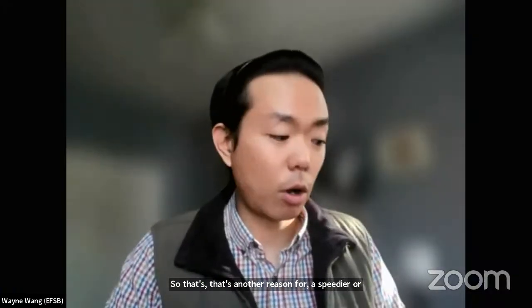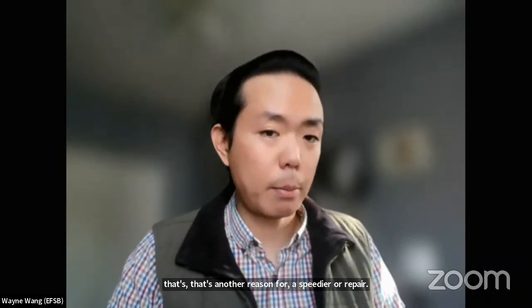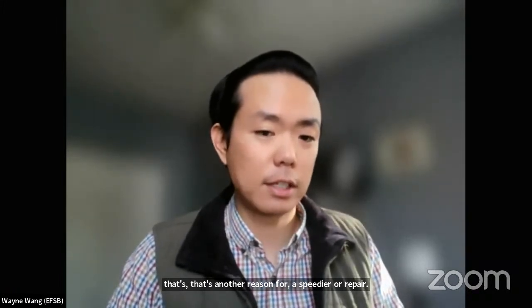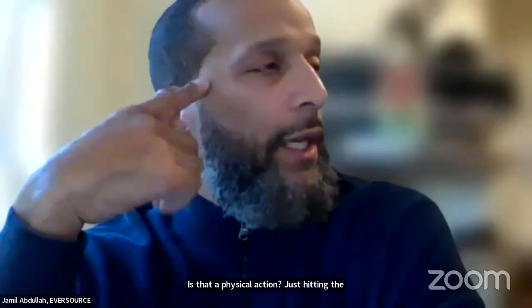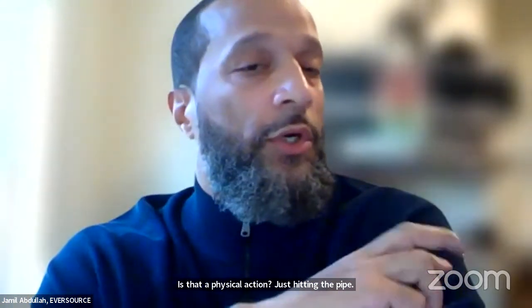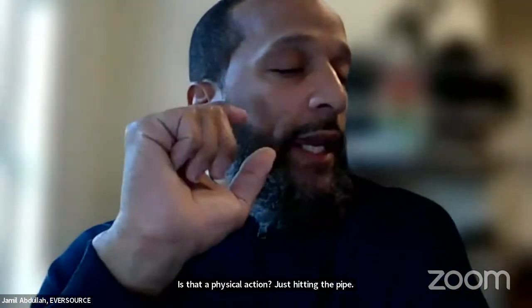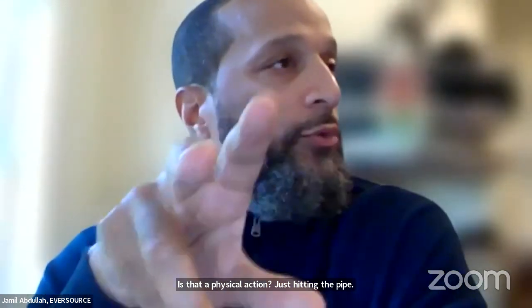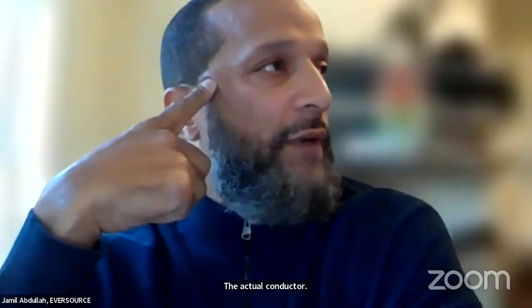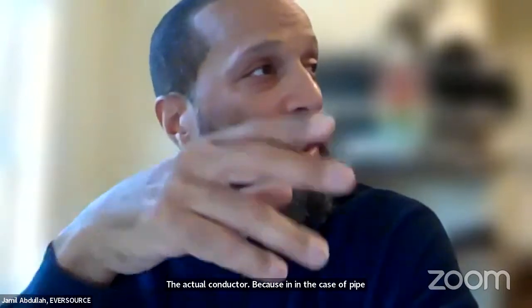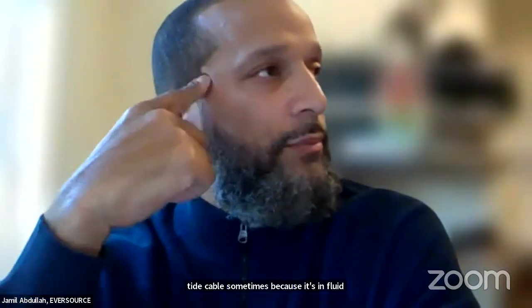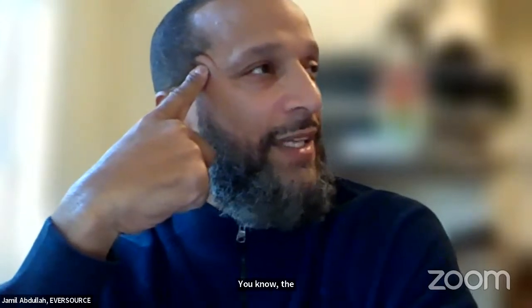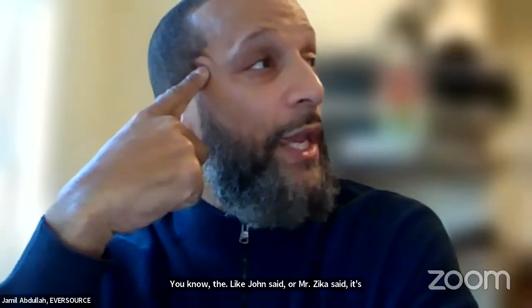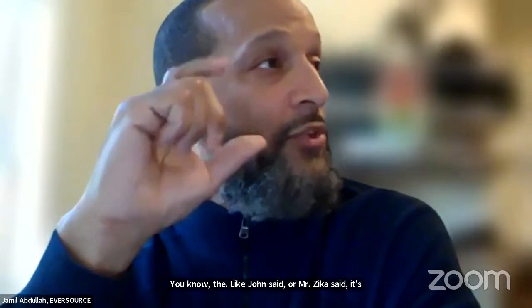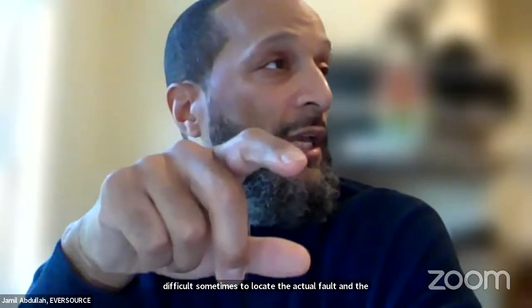Thank you, Mr. Abdullah and Mr. Zico. Mr. Abdullah, you said something about pipe thumping. Is that a physical action of just hitting the pipe? I'm sorry. Yeah, no, it's cables. So you're basically sending a voltage to the cable to burn through the actual conductor. Because in the case of pipe type cables, sometimes because it's in fluid, like Mr. Zico said, it's difficult sometimes to locate the actual fault, and the dielectric medium is fluid under pressure.